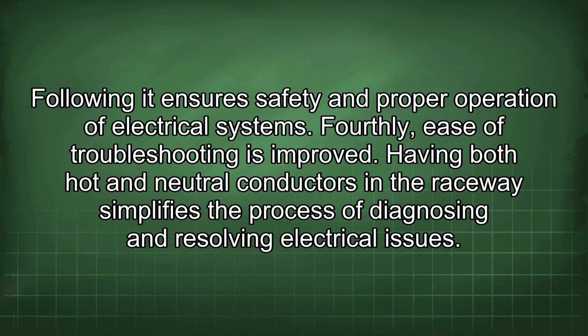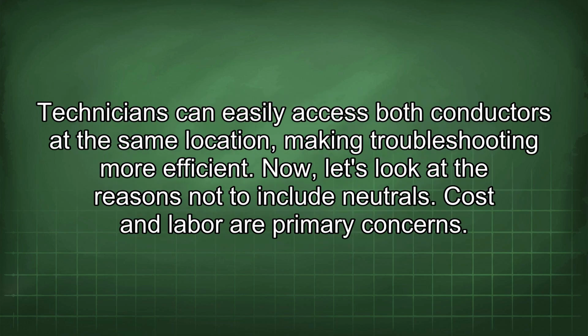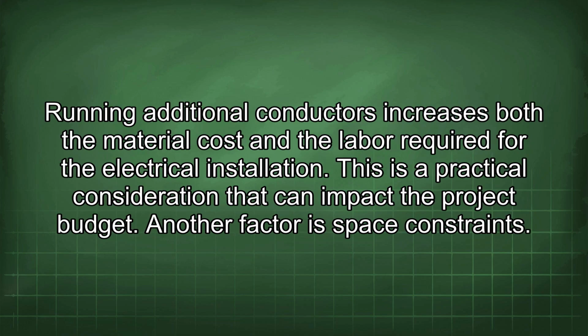Fourthly, ease of troubleshooting is improved. Having both hot and neutral conductors in the raceway simplifies the process of diagnosing and resolving electrical issues. Technicians can easily access both conductors at the same location, making troubleshooting more efficient. Now, let's look at the reasons not to include neutrals. Costs and labor are primary concerns. Running additional conductors increases both the material cost and the labor required for the electrical installation. This is a practical consideration that can impact the project budget.